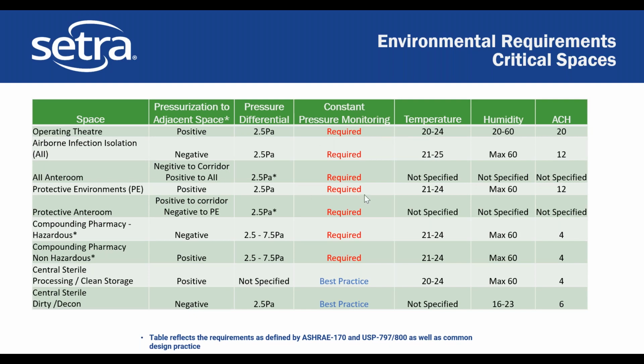All right. It should be noted that in the MEA and India regions, constant monitoring and monitoring temp, humidity, ACH, and pressure all locally at the space on a monitor is generally considered mandatory. CBAHI actually requires, and when the committee comes around to audit, they want to see ACH on the monitor. So the best practice either way is to monitor all of these parameters. In the future, there is discussion, and some spaces now as best practice are wanting to actually monitor their filter status for these spaces as well.